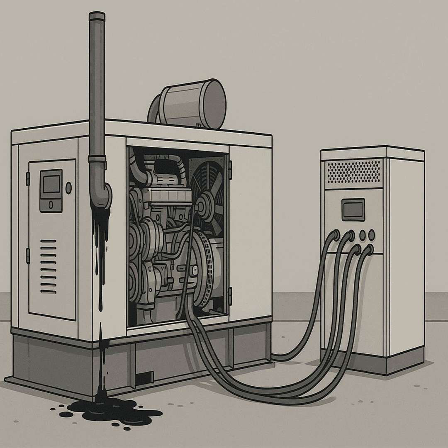Got it. So load banking is number one. What else is critical for prevention? Well, going right back to one of the main causes, correct generator sizing. This is absolutely fundamental. Don't buy bigger than you need. Precisely. Avoid the temptation to oversize the generator just in case. You really need to match the generator set's capacity to the actual loads it will be powering. And an oversized generator is practically guaranteed to run at low load most of the time, setting you up for wet stacking. Makes perfect sense.